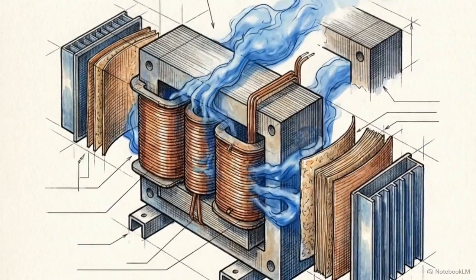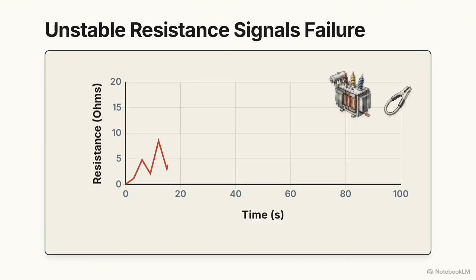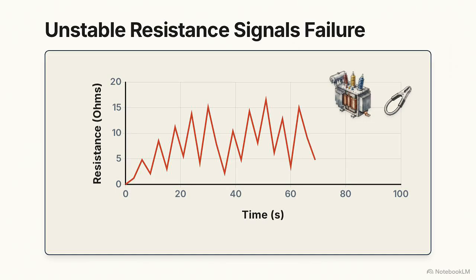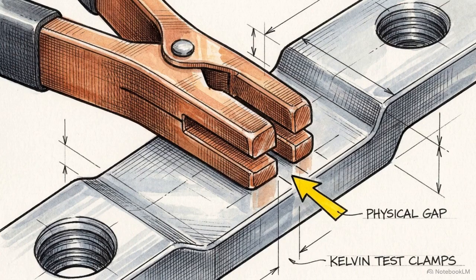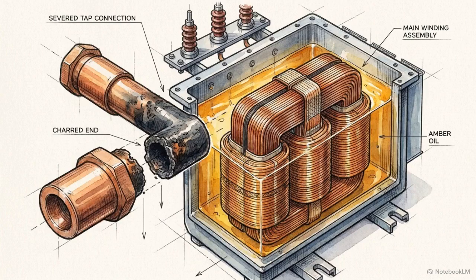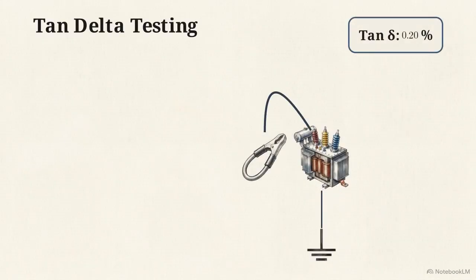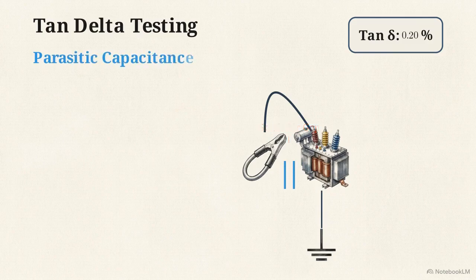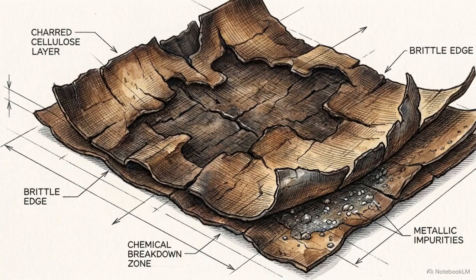If the winding resistance test yields wildly fluctuating numbers, technicians evaluate the setup. They must determine if it is a simple contact error with the Kelvin clamps or evidence of a catastrophic internal tap connection failure. An elevated tan delta reading requires similar scrutiny. A high power factor can result from parasitic capacitance if the test leads are poorly routed near grounded metal, or it can indicate genuine, irreversible degradation of the insulation paper.